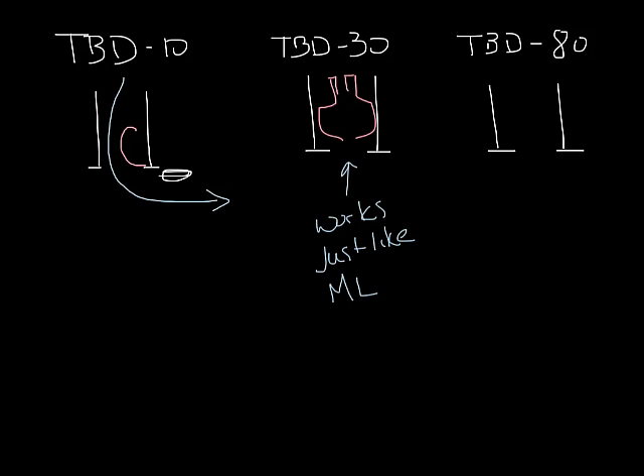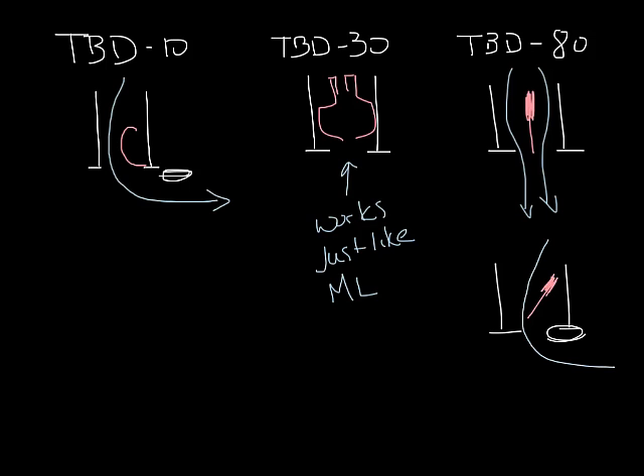In the TBD80 the pattern controllers are kind of a flat blade with a gasket on it. So this little end is the gasket. So if it's set like this the air is just going to come through and go straight down. Now if you take it and angle it to one side or the other you're going to create that low pressure zone and the air is going to come in and hold to the ceiling like this.